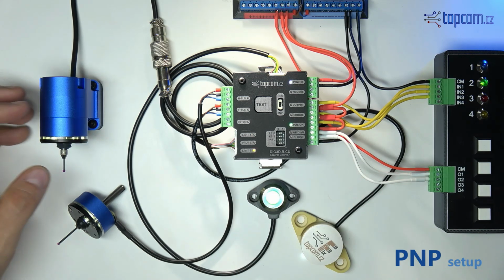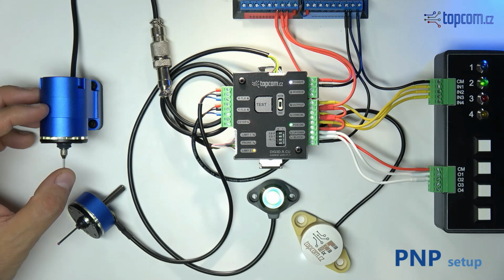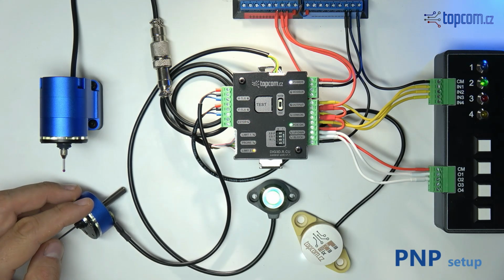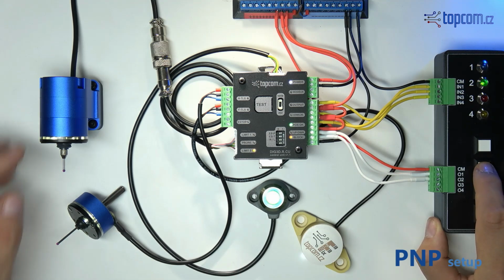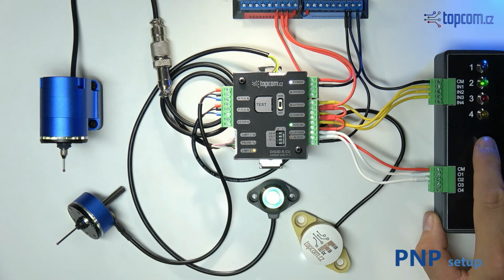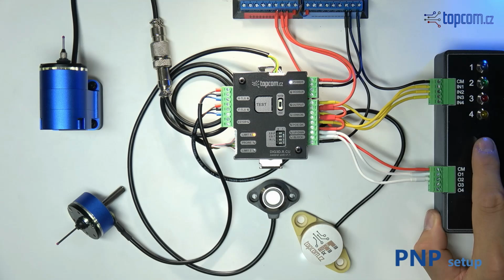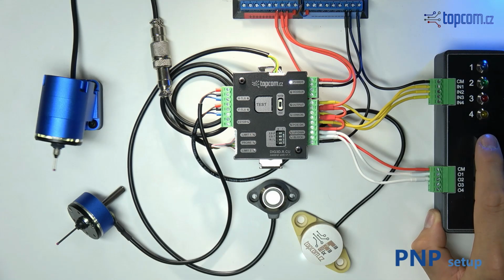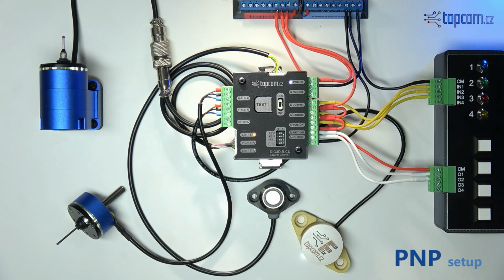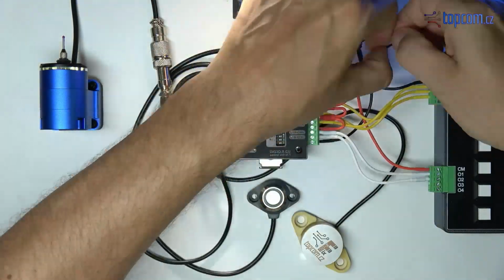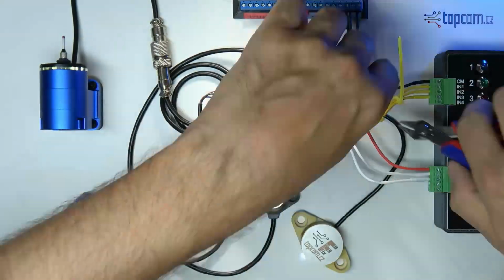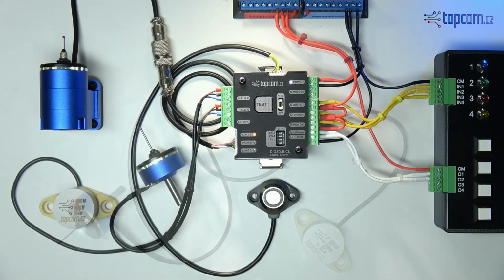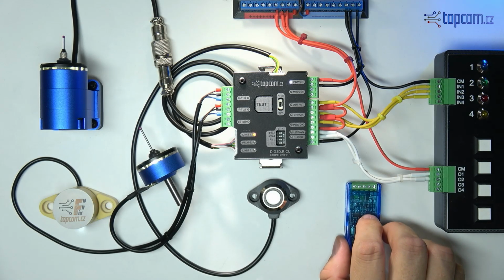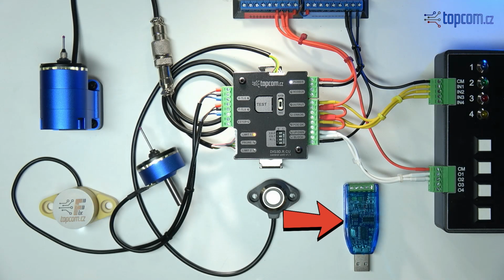Now our updated PNP setup is complete and we can once again test all the functions. This includes signal transmission from probes and sensors, the probe guard function and the block input, as well as the up-down input control. To finish, we'll tidy up the wiring and we're ready for the next part of the tutorial. In the upcoming section we'll cover how to connect the control unit via the RS485 bus. This interface allows you to configure additional parameters and control the probe using the Modbus protocol.